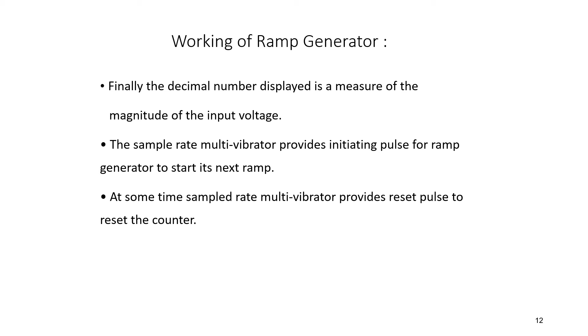So to sum up, as we have seen, the principle of ramp type digital voltmeter is based on the measurement of the time that a linear ramp voltage takes to change from 0 volts to the level of the input voltage, or to decrease from the level of the input voltage to 0. This time period is measured with an electronic time interval counter, and the count is displayed as a number of digits on an indicating tube or display.